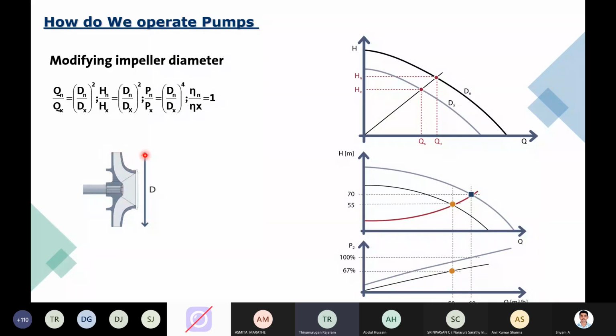Say I have a 300 diameter impeller and I want a reduced flow. You can just calculate based upon this formula, based upon the diameter for the full load, what is your head required, what is the current head, what is the flow and what is the required flow. Based upon that, you will arrive at this Dx, which is your trimmed impeller diameter. So now you can trim the impeller so that your pump will have the reduced flow, and that will also impact your energy consumption.